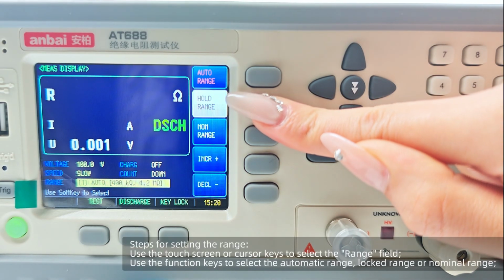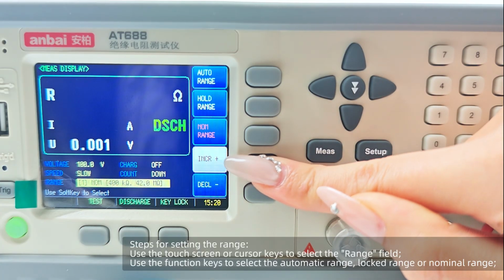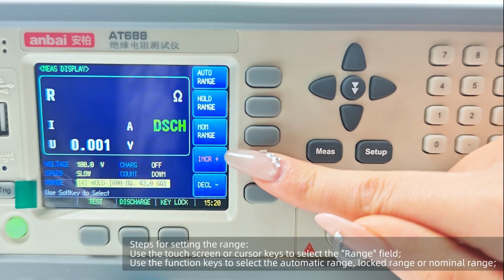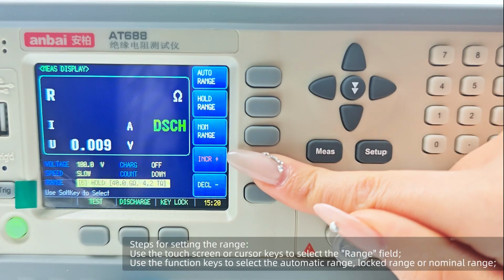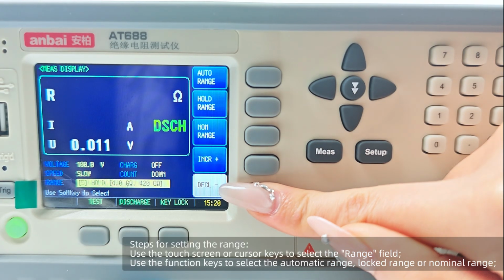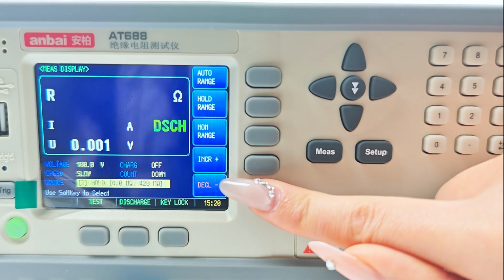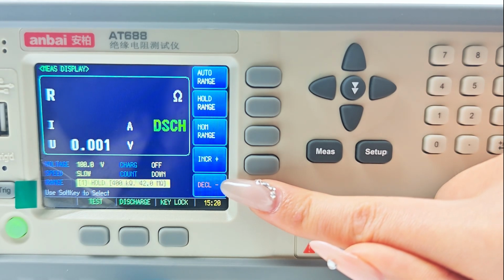Under automatic range mode, some devices may fail to select the correct range. This is a normal phenomenon. Simply switch to the locked range for testing. When measuring leakage current, it is recommended to use the locked range.